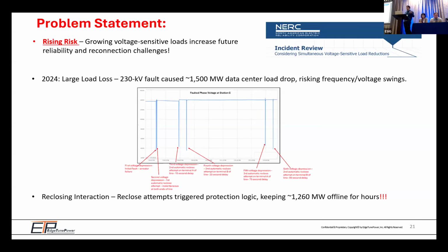And the utility got surprised because the utility was like, no, you have to reconnect because I am losing 1.5 gigawatt load, which can result in instability of operation of my system. So I said, please reconnect. And the load was like, no, I don't want to reconnect again. I feel there is a small voltage disturbance at the point of interconnection. And this story happened again and again and again. So as you can see on the picture over there, we have almost 6 attempts of reclosure of the large load to the facility, which is showing that the problem can start from control, it can go to protection, it can go to lack of control and protection coordination for data centers.